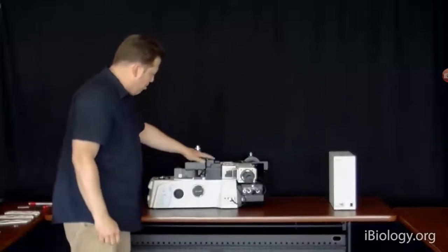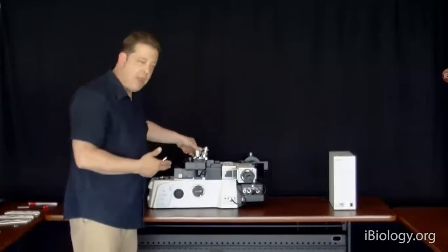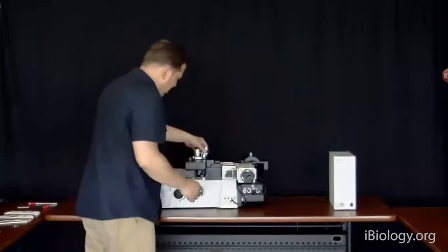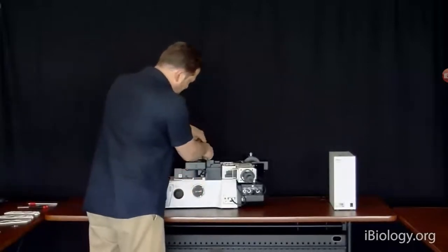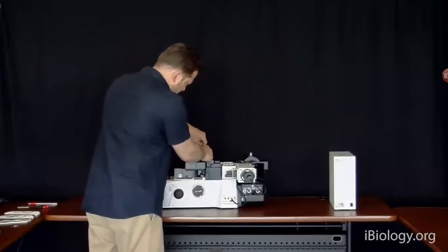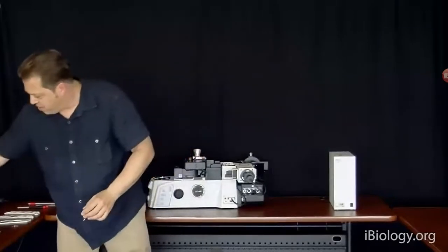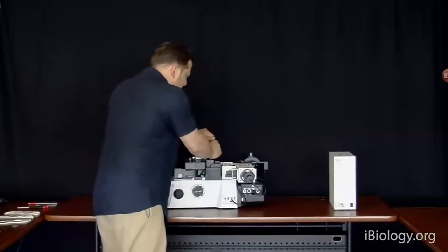Here we have what's called the nose piece of the microscope, also known as the objective turret. The nose piece has a motor in the center, and you can see it holds multiple objective lenses. Currently, it's got one 100x TIRF lens. Put that off to the side. And then we will remove this component.